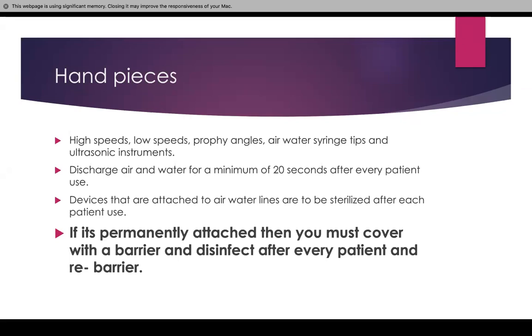Devices that are attached to air-water lines are to be sterilized after each patient use. If it's permanently attached, then you must cover it with a barrier and disinfect with a medical-grade disinfectant after every patient, and then re-barrier it. You cannot keep the same barrier — those blue barriers we usually use cannot be reused for the next patient.